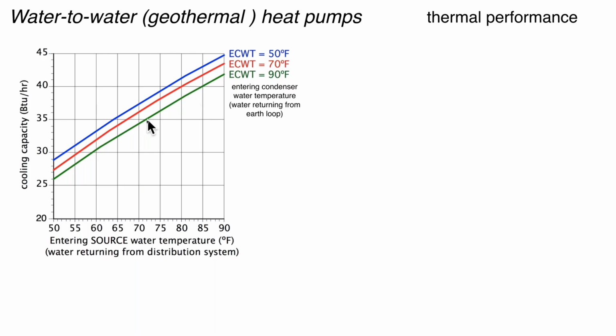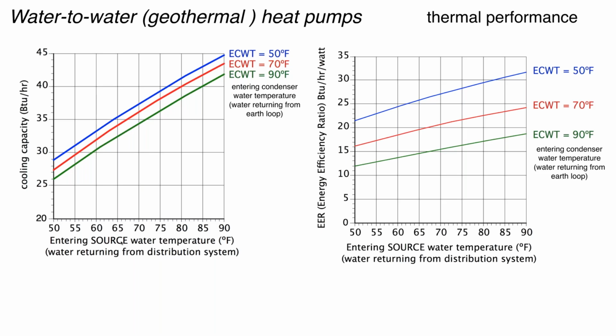And we also drop in cooling capacity as our entering source water, now this would be the water coming back from the cooling coil in the building, as that temperature goes down, our cooling capacity goes down. So net effect is really the same as what we have with air to water heat pumps. The numbers could be different, but the trending is the same. And it's also true with energy efficiency ratio. The warmer you can keep your chill water temperature and the cooler you can keep your earth loop, the higher the energy efficiency ratio, as well as the higher the cooling capacity of the water-to-water heat pump.